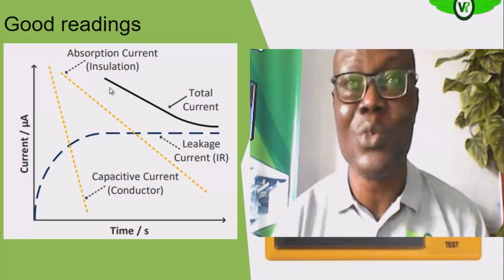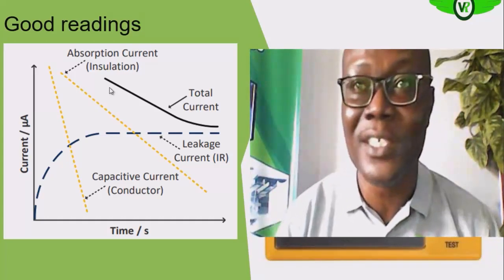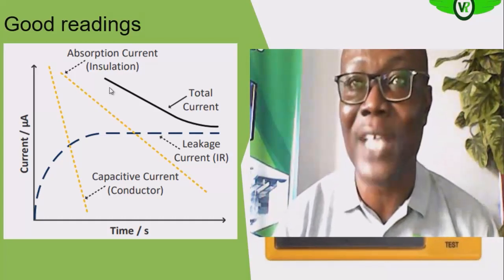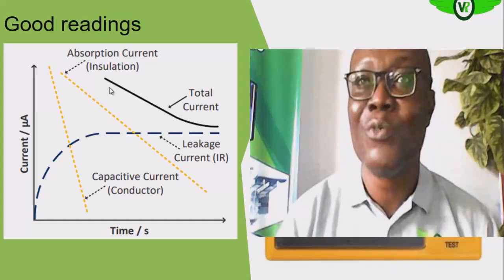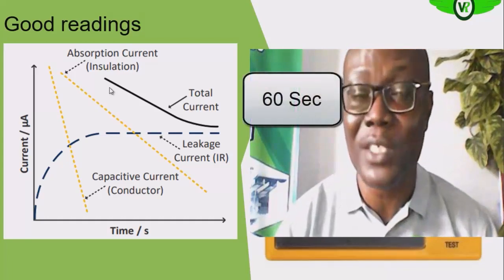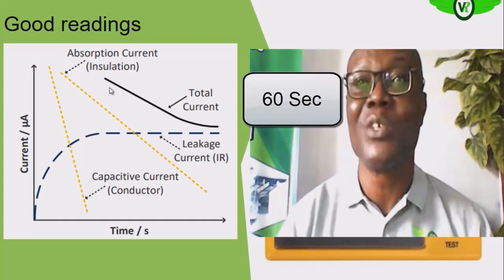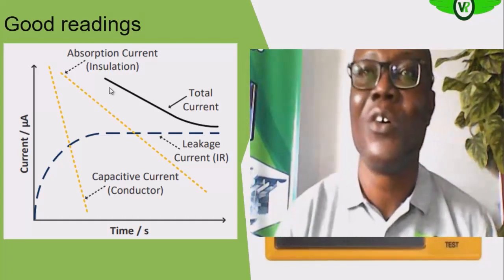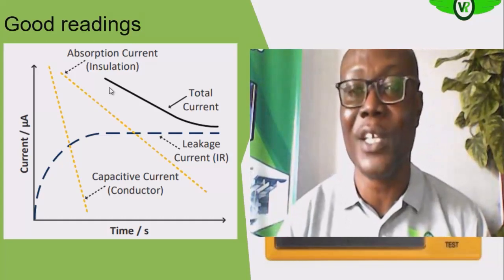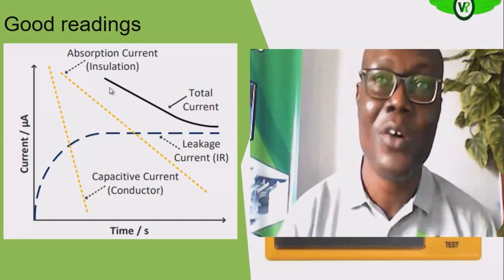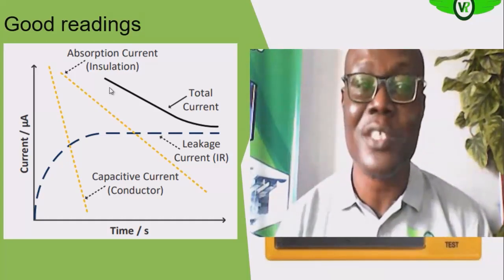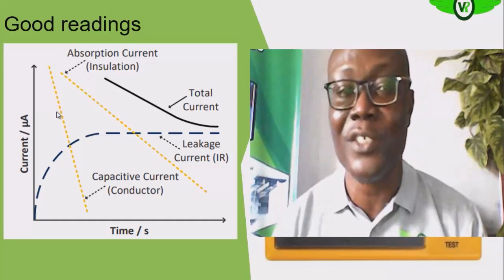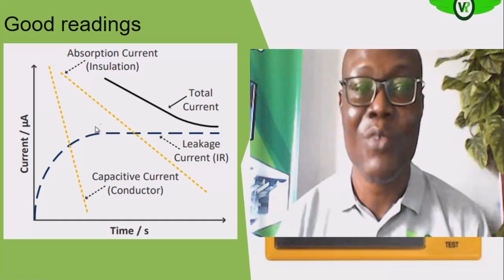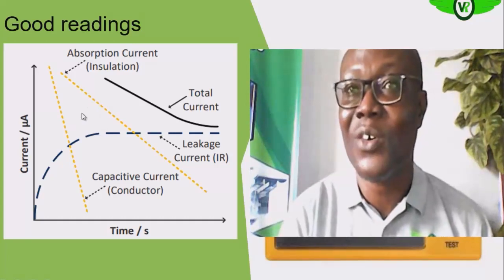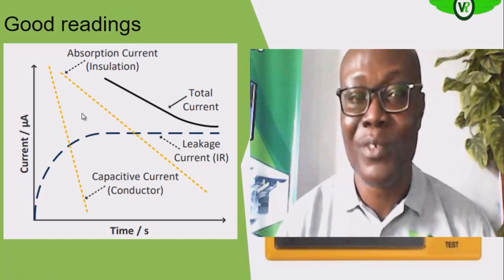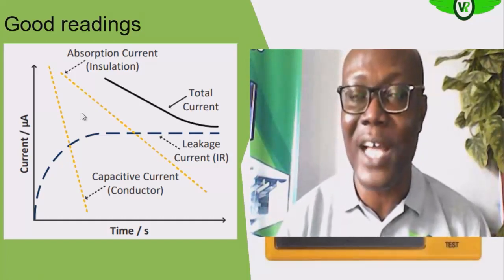So the most ideal time for you to take your IR reading after injecting your test voltage, or when doing IR test, is that you allow 60 seconds to pass. That is 1 minute. It's a must. Okay, that is when you will have the accurate reflection of the insulation resistance of the equipment, or the insulator that you are testing. So if you record the reading before 1 minute or before 60 seconds, what you are having will be reduced insulation resistance, that is reduced IR, because of the higher total current.